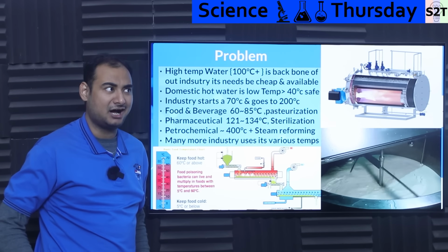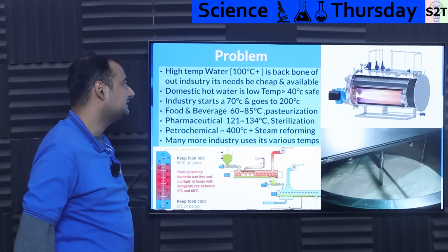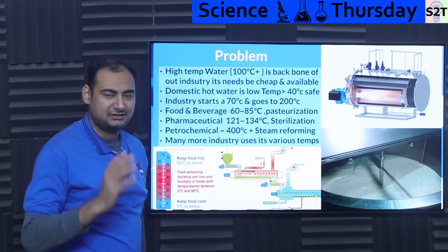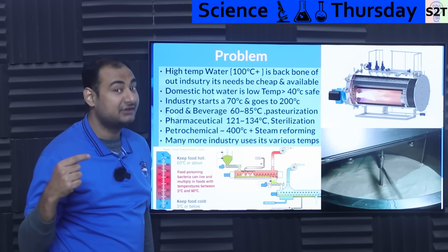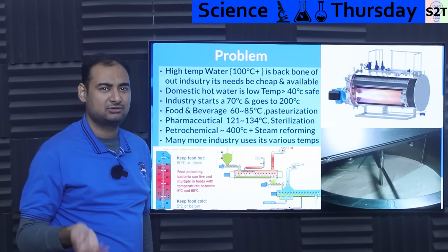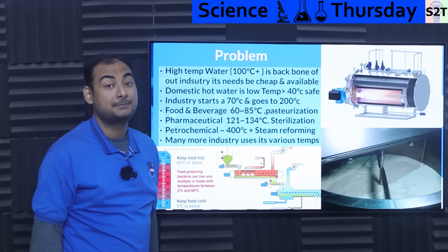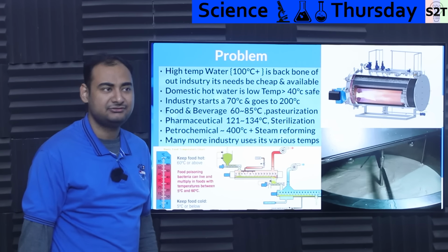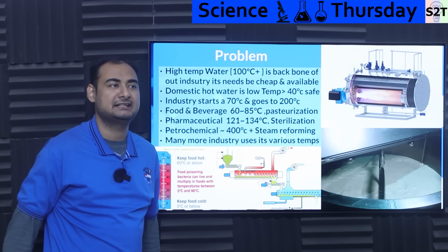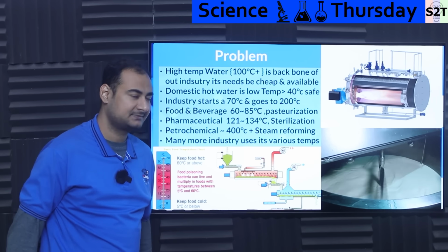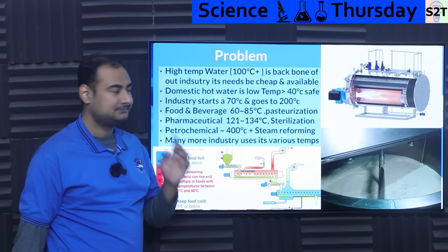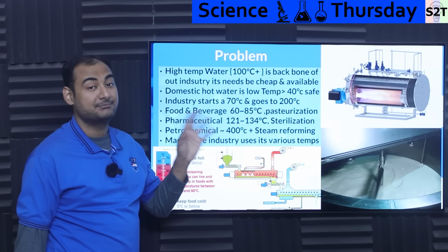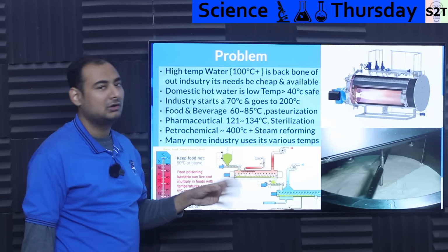Why the heck do we need high temperature heat pumps? Well, reality is that high temperature water, generally temperature of water above 100 degrees Celsius. You're like, okay, how can water be above 100 degrees Celsius? Pressure. You increase pressure high enough, you can get it to still be water as high as 200 degrees Celsius. So that is normal, and high temperature water is the backbone of all our industry.